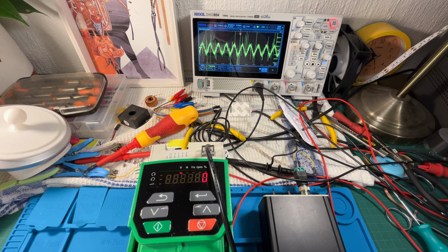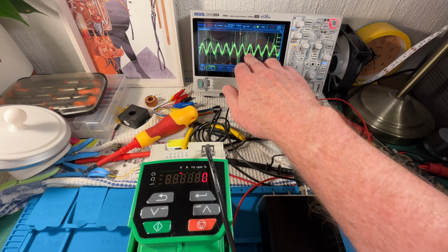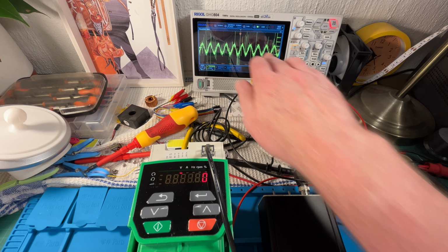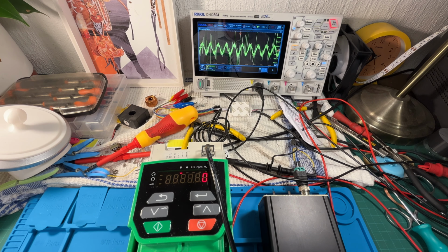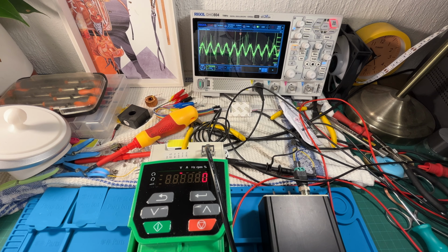One's just got to be aware that you're in constant power at this point. So you've got to rate your motor to suit the power that's going to be absorbed when you overspeed it slightly. Generally we go for a maximum of about 70 Hertz, which would be about 40%.